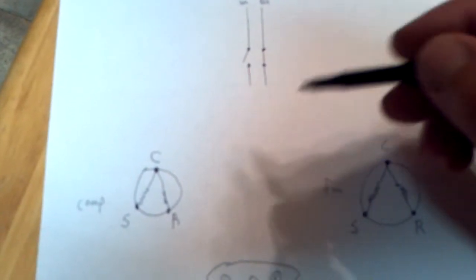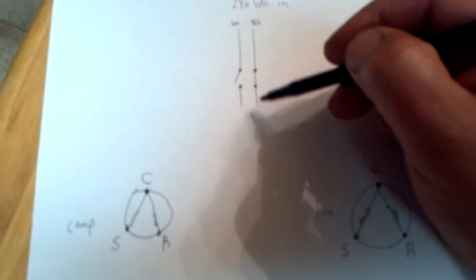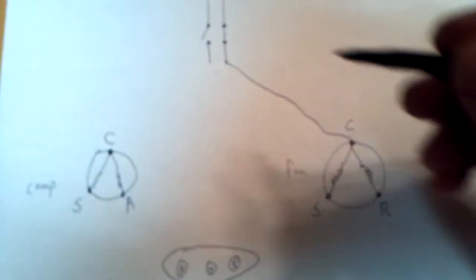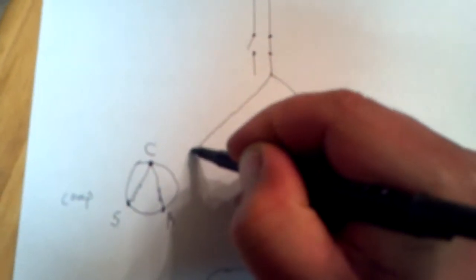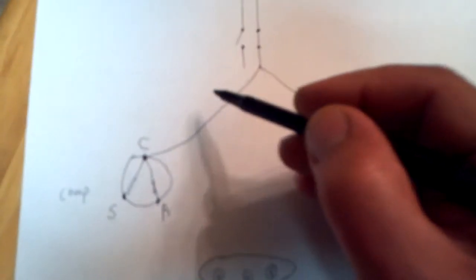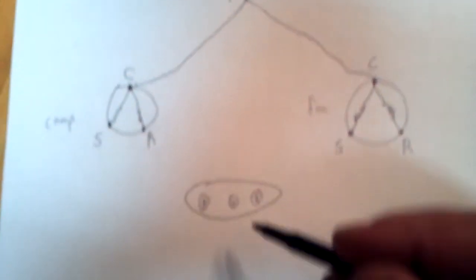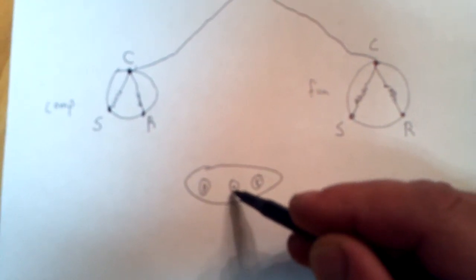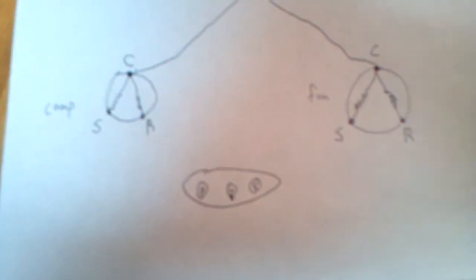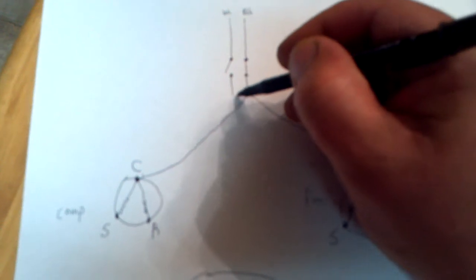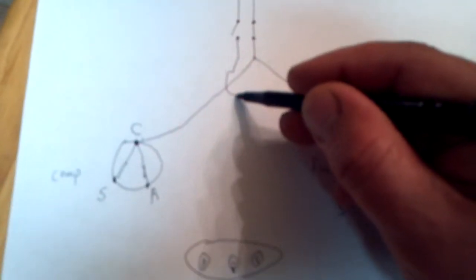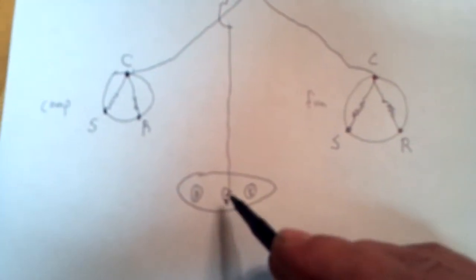So how we, if we have a single pole contactor, how we normally wire this up is, this black wire here, the unswitch leg. That just goes straight to common. So this will be like to your black wire coming from your fan motor. And we'll take this wire. Or there should be some, many times it would be blue or yellow or what have you. That'll go to also the common. So see, the commons on the fan motors is totally not the same as the common on your dual run cap. Actually, we might call this the run winding terminal.